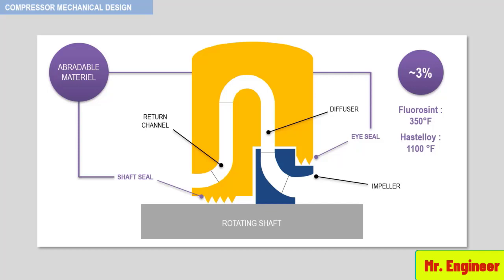One note of caution regarding Fluorosint labyrinths is that they should be pressure-balanced. Pressure balancing of each interstage labyrinth ensures that the high-pressure side of the seal — for the eye seal and for the shaft seal — will not deflect or force the material into the rotor surface. The lack of pressure balance will result in wear of labyrinth seals.